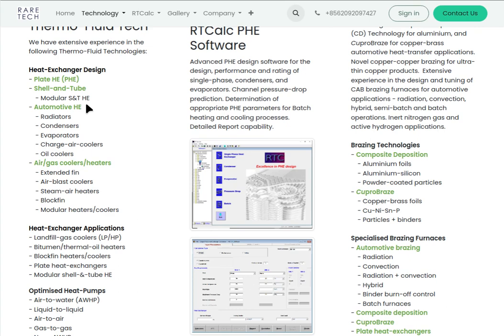We were getting heat transfer predictions within less than 3% out, and pressure drop within 5 to 8%, where most people can't get closer than 30% on pressure drops. So we got very close.